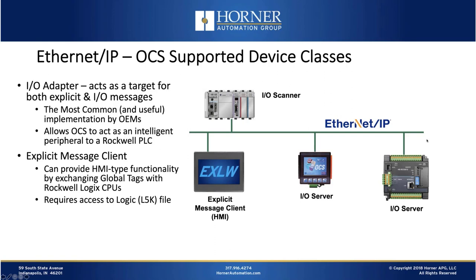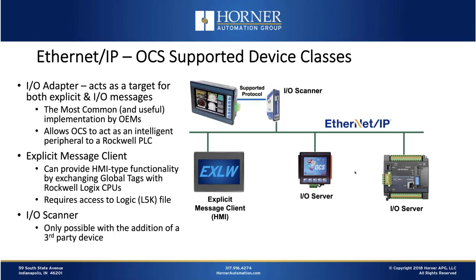You don't need to choose between having the Horner controller act as an I/O device or an HMI device — you can configure it to be both at once. For those wanting the OCS to act as an I/O scanner and effectively run an Ethernet IP network — maybe because you use drive adapters or other specialized products with Ethernet IP interfaces not available on other fieldbus networks — in that scenario the OCS can be an I/O scanner, but only when connected to a third-party device that acts in that capacity. We have interfaced with I/O scanner companies like Real Time Automation out of Wisconsin, as well as devices from Hilscher and HMS. So it's definitely possible, but it does require third-party hardware.